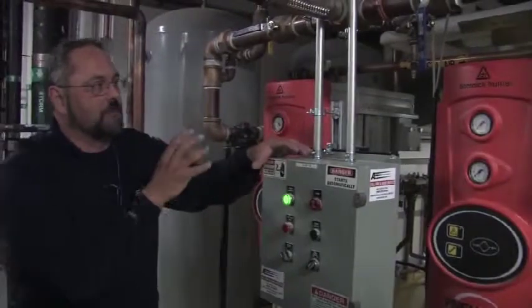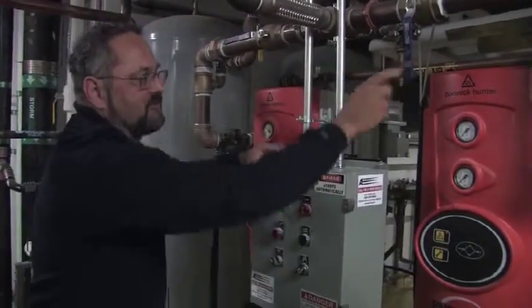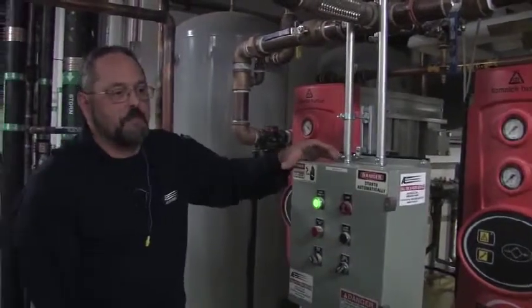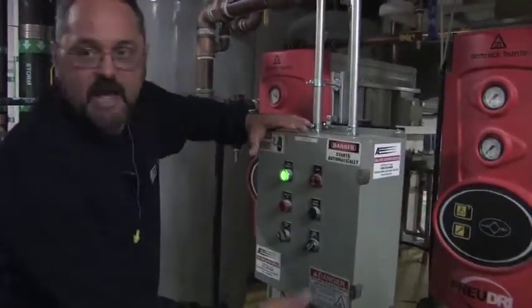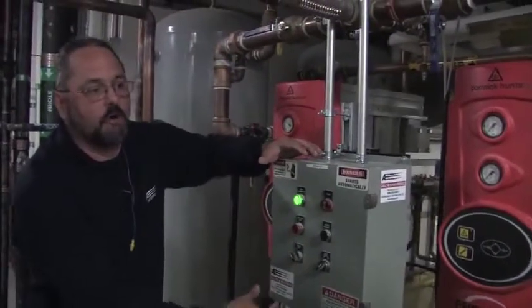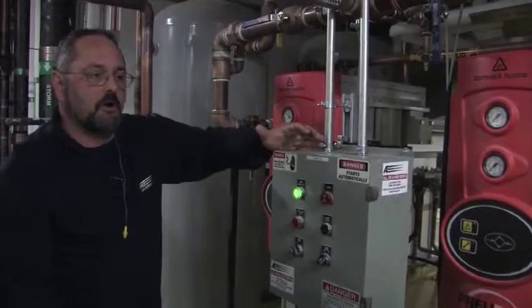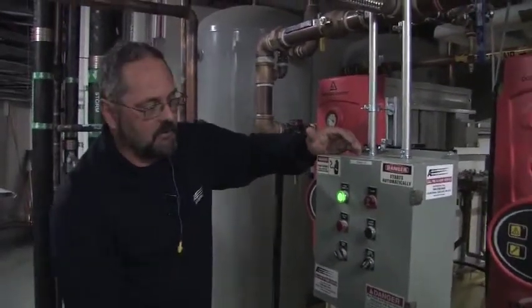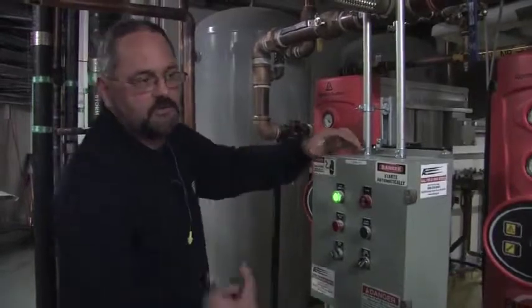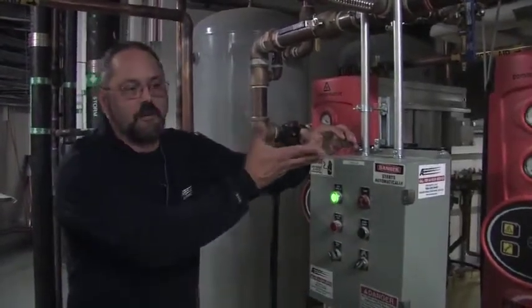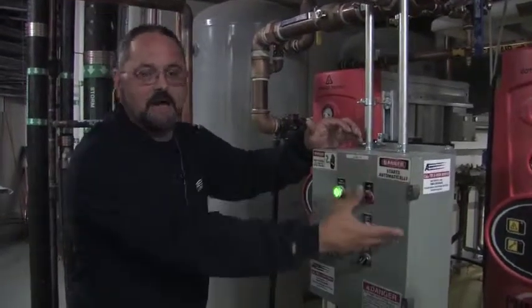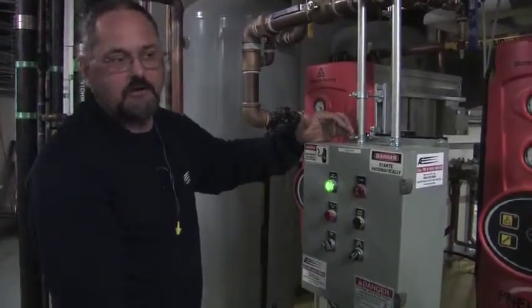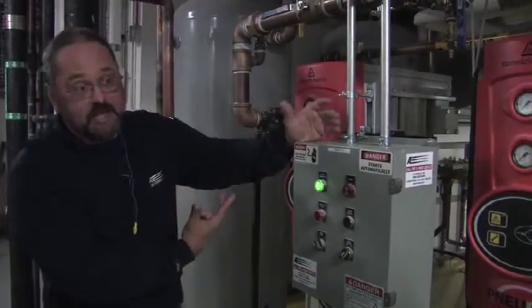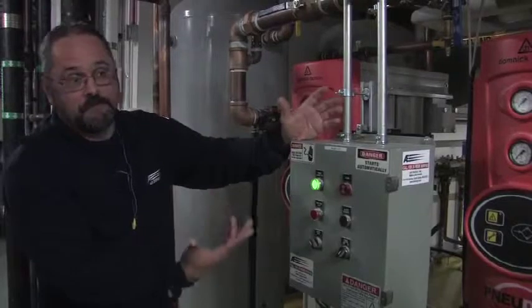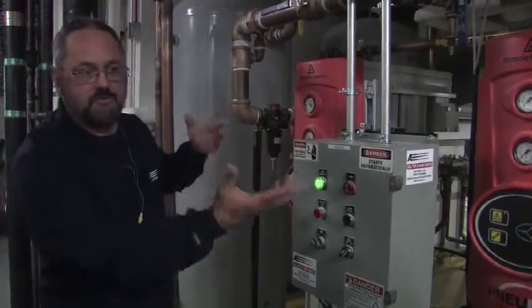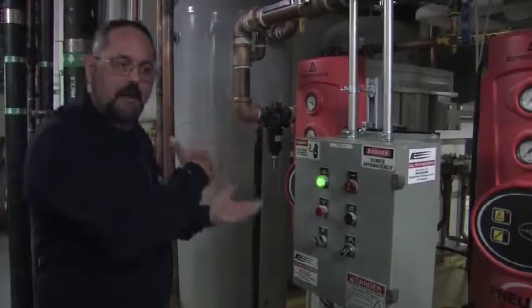The reason for powering it off, lots of guys will just shut the valves but not power them down. The problem is if you leave the power on, the solenoids keep actuating, letting the muffler port open to atmosphere in the room. So if you let it be the backup for 3 months, whatever ambient moisture is in the air goes in through those solenoids and saturates the desiccant bed. So when you turn it back on, it's wet. And you've got to run it for 12 to 24 hours to dry it out before you can put it online. Ideally you're going to be doing it once every month or once every 3 months, whatever your routine is, because that's just how you balance them out.